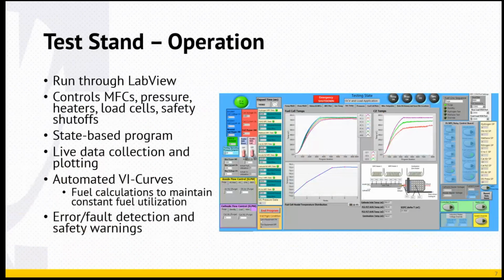Our test stand runs through LabVIEW, and it's a state-based program. We have different states for warm up, cool down, purge, standby, hydrogen test, and various other things. It's able to communicate with all of our sensors, mass flow controllers, pressure regulator, heaters, and load cells, and it operates those and collects data from them in real time so we can view it and run our tests how we wish.